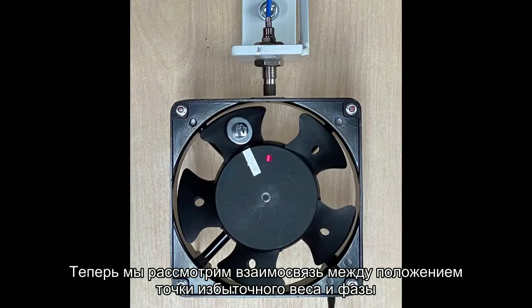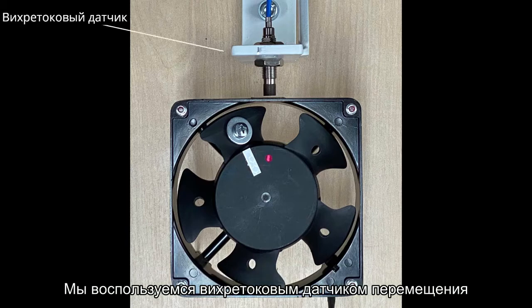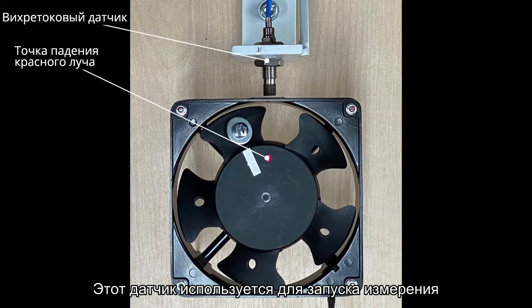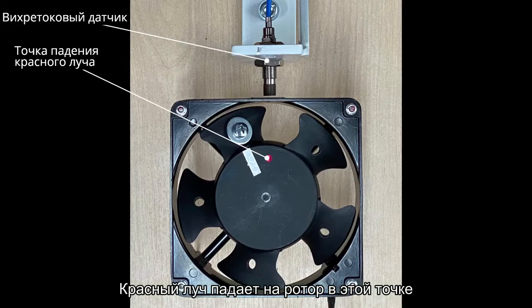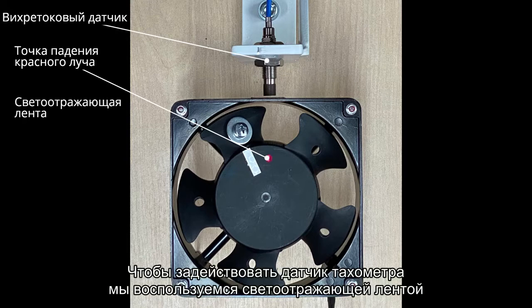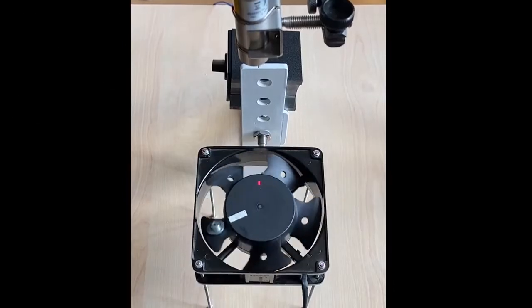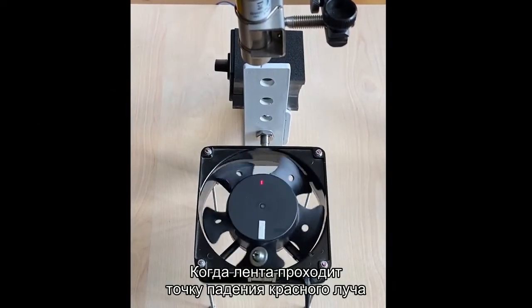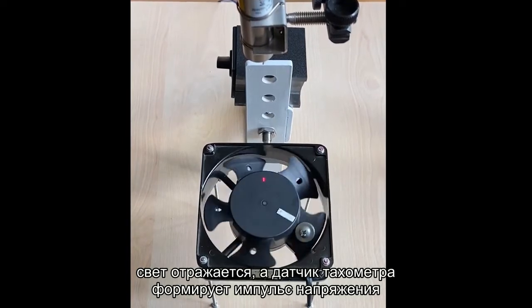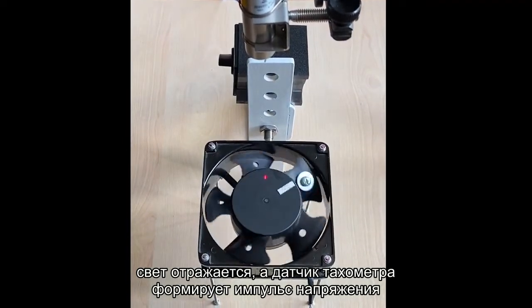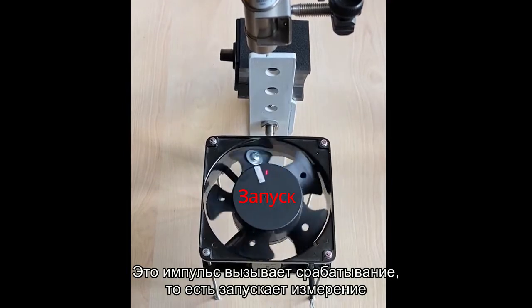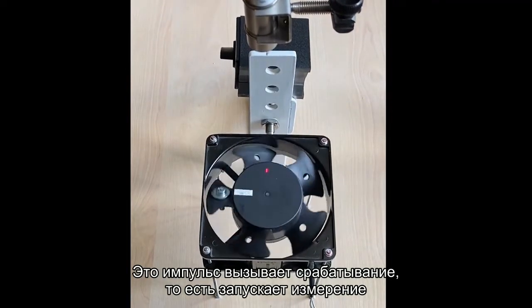Now we explain the relationship between heavy spot position and phase. We use the displacement eddy current sensor. The tachosensor is used for measurement triggering. The red ray shines here on the rotor. We use the reflective tape for the tachosensor. When the tape is going through the red ray point, the light is reflected and the tachosensor creates a voltage pulse. This pulse triggers, it means starts, the measurement.